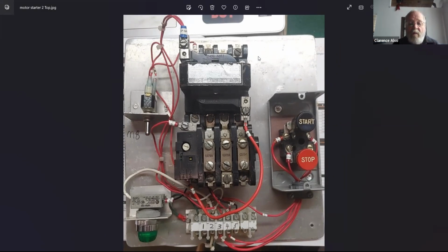Now you see the one we have, terminal number 6 -- that's the 6 side of the coil. This is the one that went to the overload that tripped out. It had one set of terminals. It might have 3 thermostats, but just keep in mind it's got one set of terminals, so that's all you've got to know. When it pops out, it makes no difference to you.